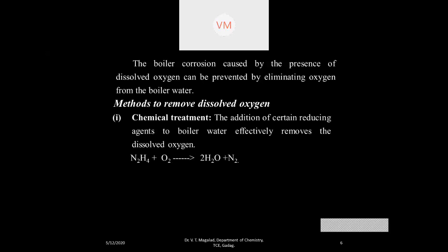We can adopt some chemical treatment as well as some physical treatment. Chemical treatment, what we can do? There is some chemical called hydrazine. So hydrazine means N2H4, it is a hydrazine. This hydrazine is added into the boiler feed water.